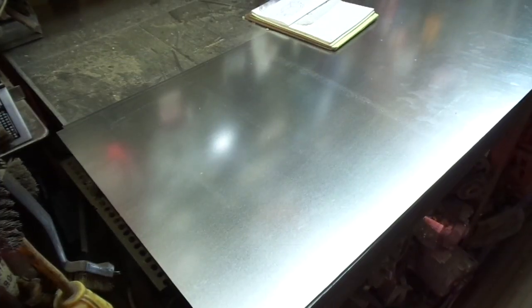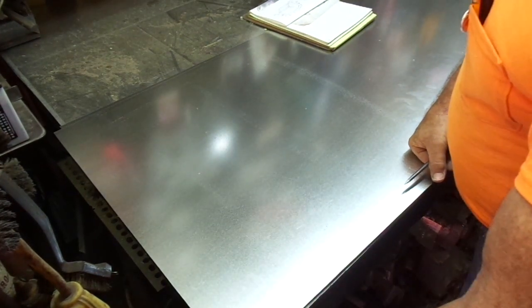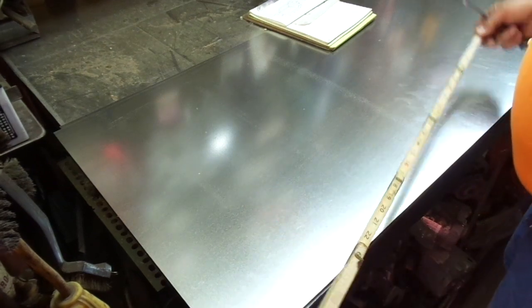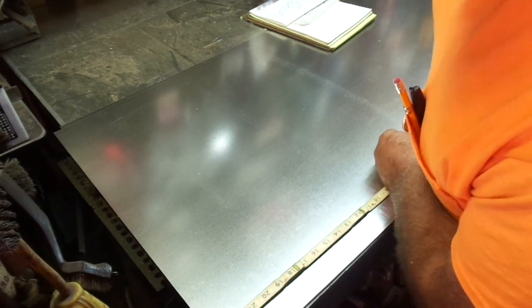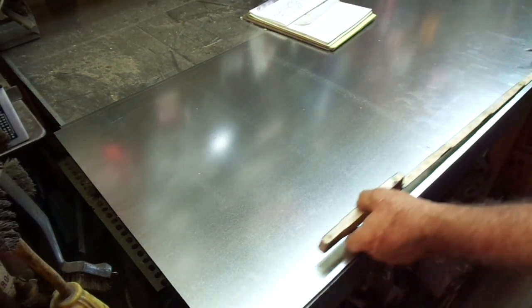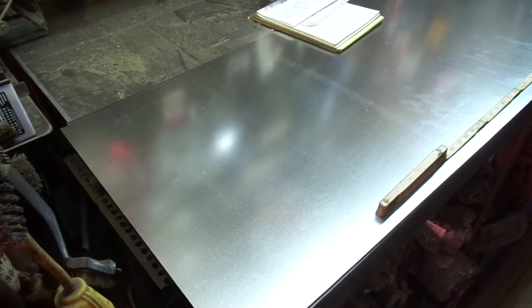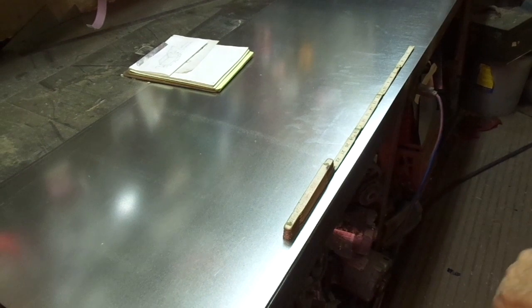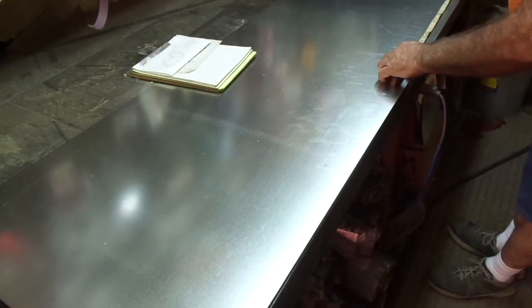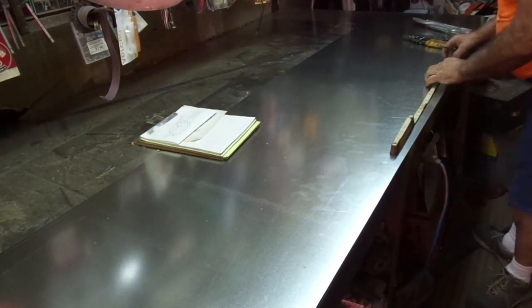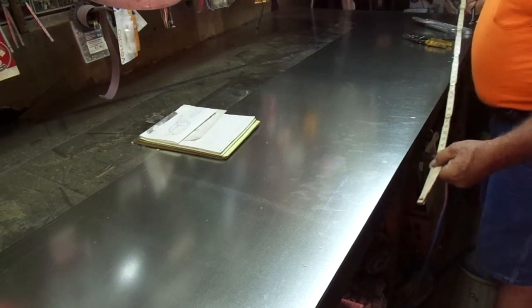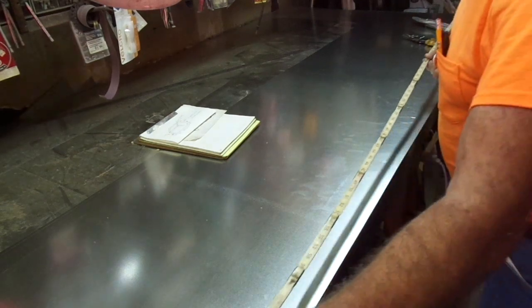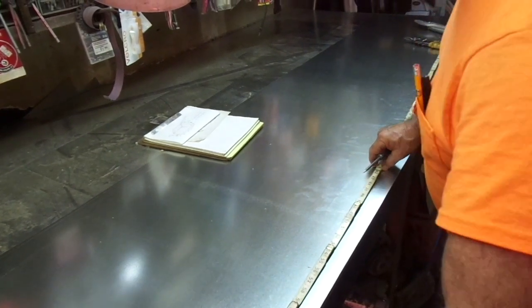So that's what we're going to do now is lay this out right here, run it through the lock forming machine, get that prepared, make the two plugs, put that in, and assemble that. And the furnace will set directly on top of it. The furnace has provisions for the filter in the bottom of the furnace. The return air comes right down and slides right up against this, and we'll have to dovetail the fittings on the job site in order to connect up securely and tightly. So what we'll do, we'll start off with the two inch measurement here. Then we're going to add the height of it, so that's going to be 21 and a half.